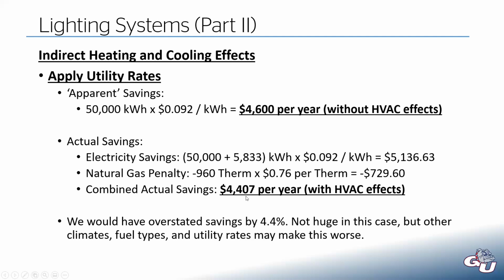The combined actual savings after accounting for all that is about 4,400, which is a little bit less than what we had calculated up here. In this case, it wasn't as prominent. 4.4% overstatement on their savings. But if this was different, if you were in a climate where they were in heating mode more often, or maybe they paid more for their gas and less for their electricity, that can skew this analysis in any way.